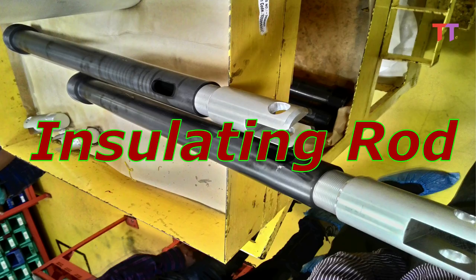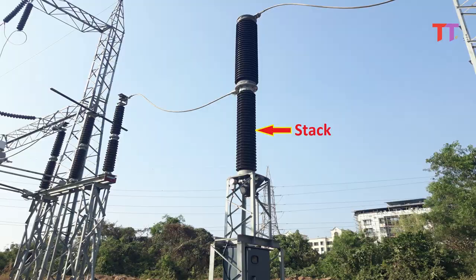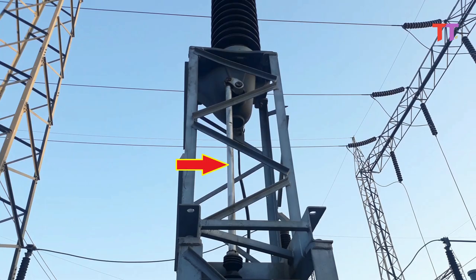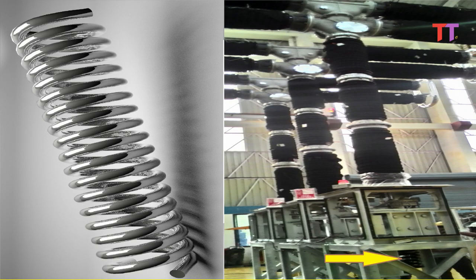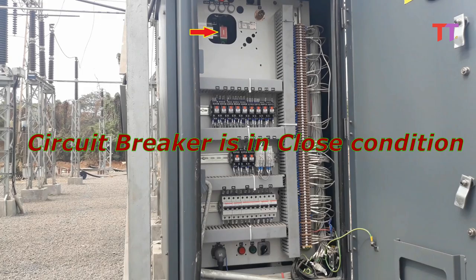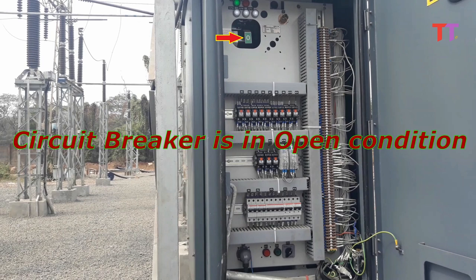As discussed in last video, insulating rod which runs through this stack is coupled with this rod, which is again coupled with spring. Here we can see spring which drives the rod during operation. We can see indications, one in red color appears when circuit breaker is in closed condition, and zero in green color appears when circuit breaker is in open condition.